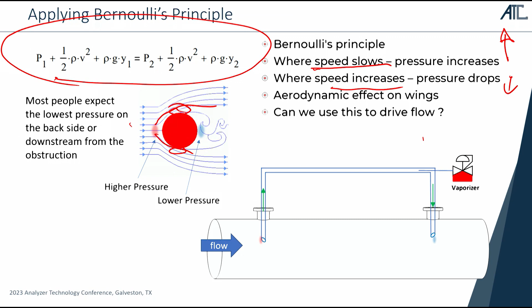You can see what happens as the flow increases: the red zones show low pressure building up on the side, and there's a little blue spot right at the front, in front of the probe, which is actually a low pressure zone. Then you see the Karman vortices forming—these are the things that cause flow-induced probe resonance—and then they slow the flow back down again. It's a kind of cool little video.